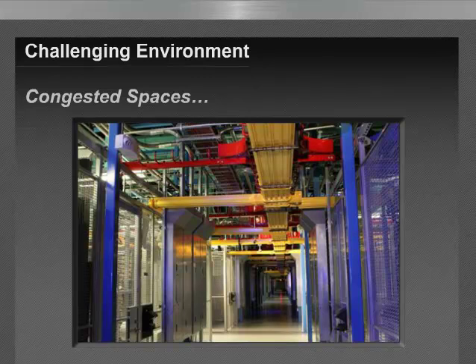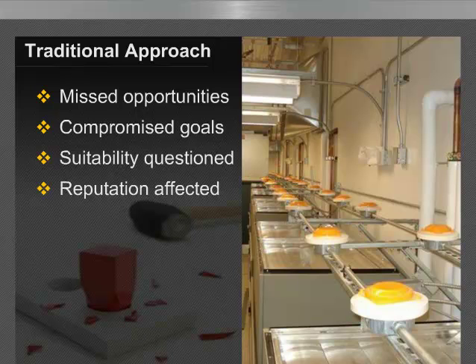With this particular picture, it is quite surprising to see this application, but what we're trying to show here is that this application is kind of like fitting a square peg into a round hole. Here's an application where the intent was to detect smoke coming into the HVAC system using conventional detectors, or a traditional approach, if you might say. The point to be made is that there's a missed opportunity to take advantage of design efficiencies using appropriate technologies, resulting in lower return of investment, plus supervision. I mean, the fire panel has no idea that the dust covers are on these detectors. It's fat, dumb, and happy sitting on the wall thinking everything's okay. So there are some definite missed opportunities.